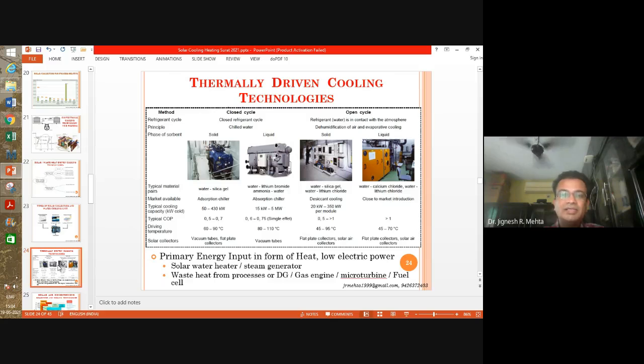So here there is a table given where different technologies for producing chilled water, or you can say water chilling plants, or basically producing cold, different technologies or equipment have been shown. So one is working on closed cycle, another on the open cycle. Open cycle is nothing but desiccant based systems, and in closed cycle you can have absorption or adsorption. So the first column is for adsorption, and the size of systems for which it is normally used has been mentioned here. Adsorption is used for 50 to 430 kilowatt; you can divide it by 3.52 roughly to get tons of refrigeration.